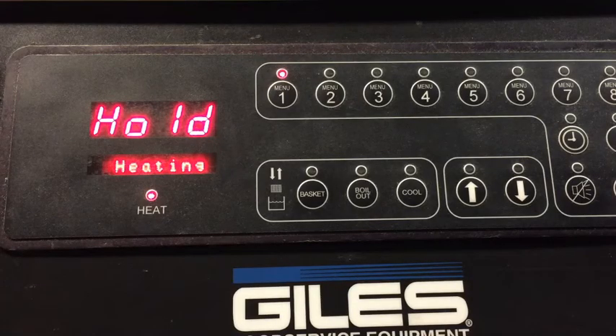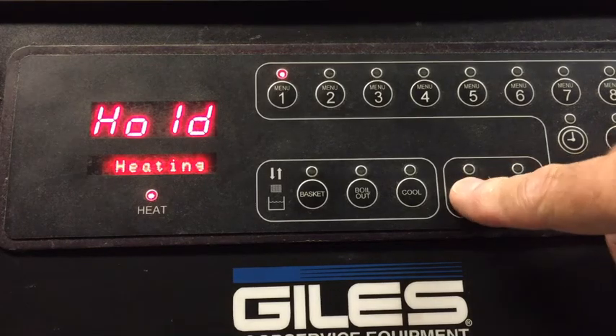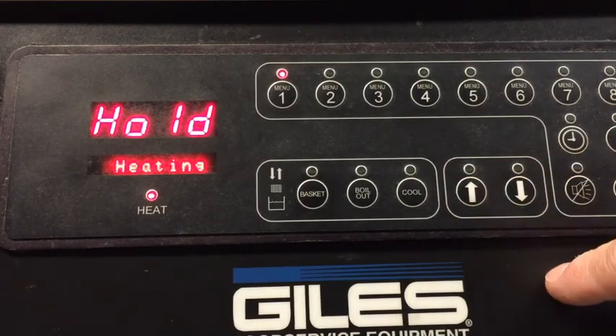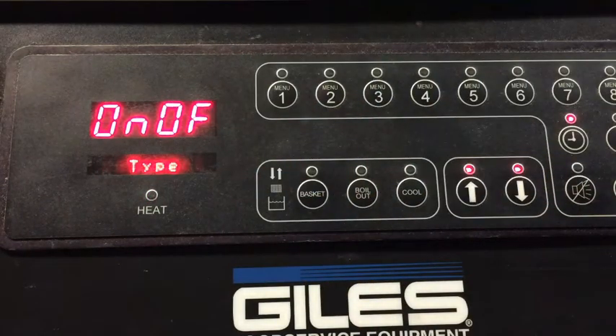Service mode technician programming for the N7, and this is actually technician only type programming, but to get into it is fairly simple. You're going to press the up arrow, then the down arrow, and then the basket key 2 times, and you see it comes up, it says type on off. That's the relay control, and you always want to leave that at on off.